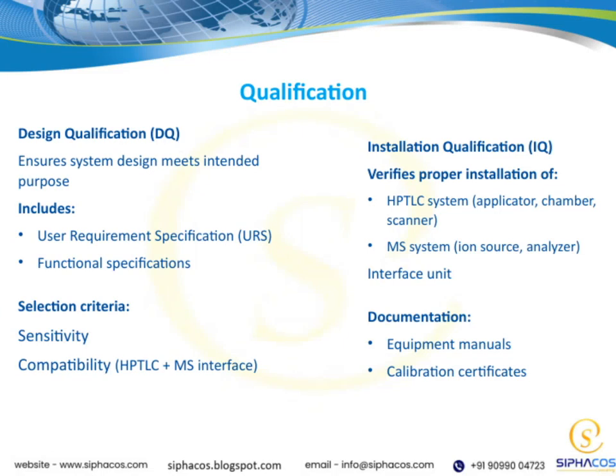Now, let's look at installation qualification, or IQ. This step is all about verifying that the system has been installed properly. We want to make sure that key components like the HPTLC system, this includes the applicator, chamber, and scanner, as well as the MS system, which involves the ion source and analyzer, are all correctly set up. Additionally, the interface unit connecting these systems needs to be properly installed. Documentation plays a crucial role here. We'll review equipment manuals to ensure everything is installed as per the manufacturer's instructions. Calibration certificates are checked to confirm the instruments are calibrated correctly. And of course, we document all these steps thoroughly as part of the qualification process.